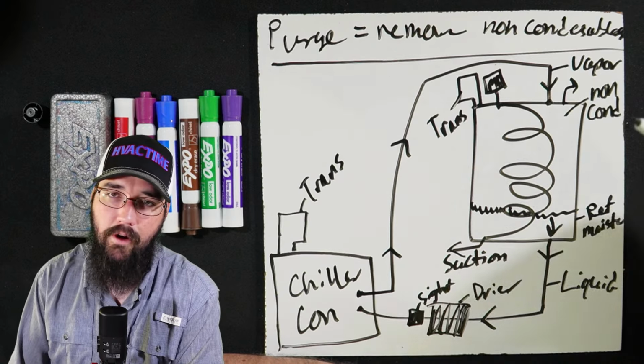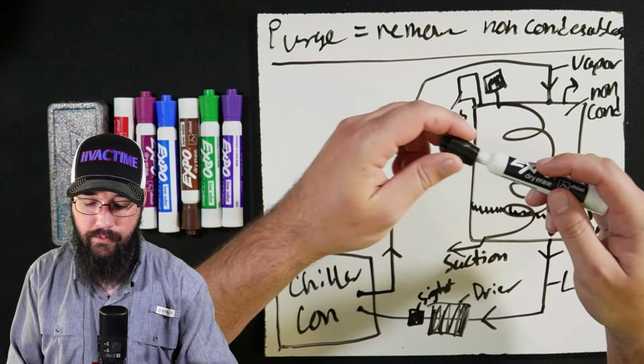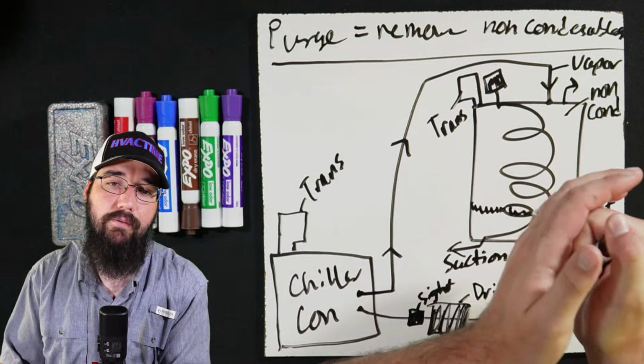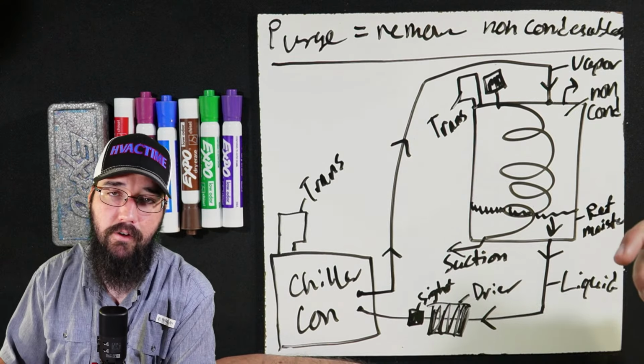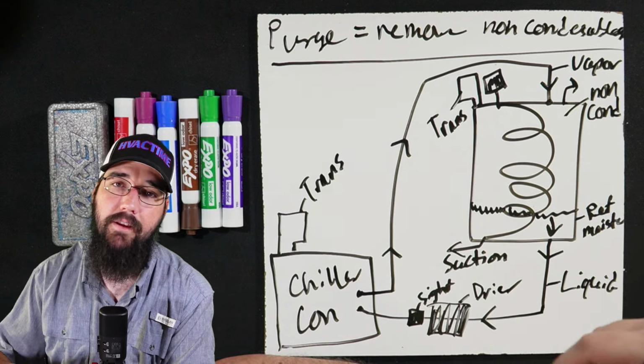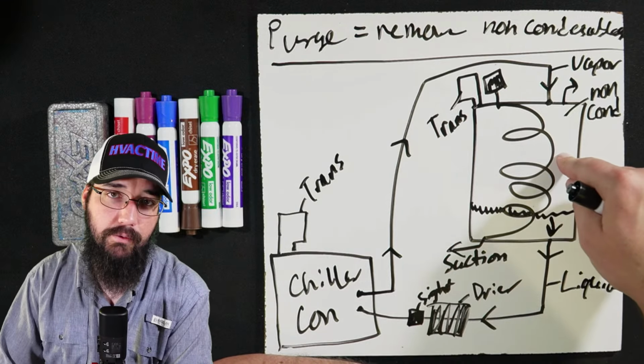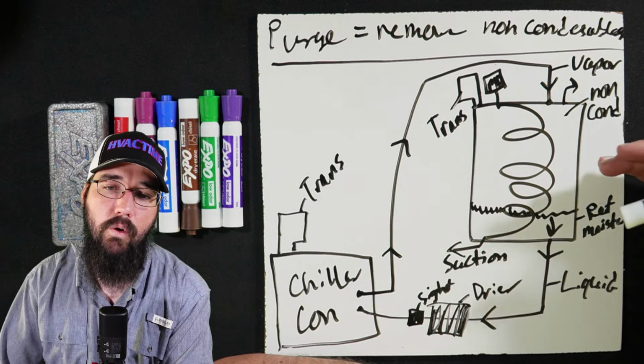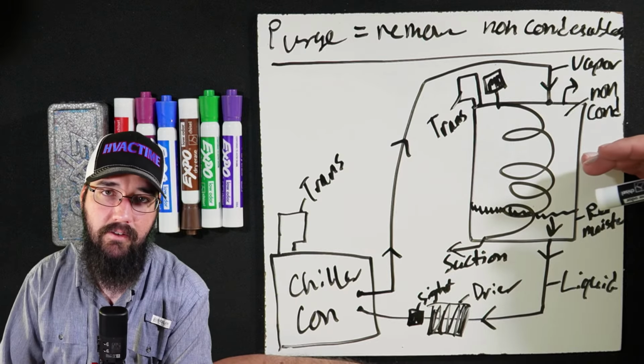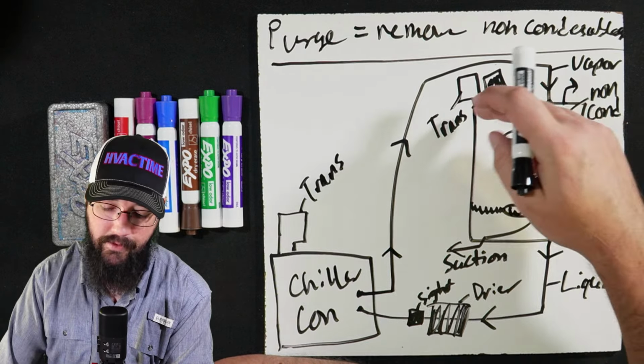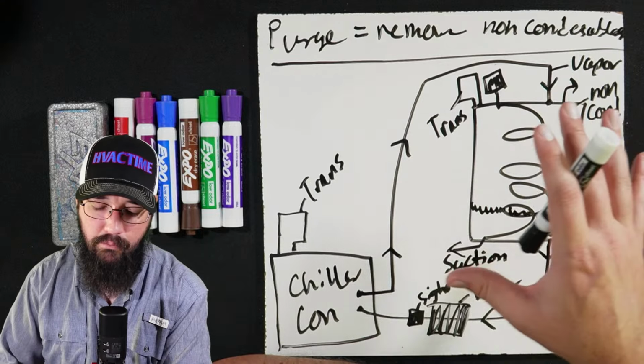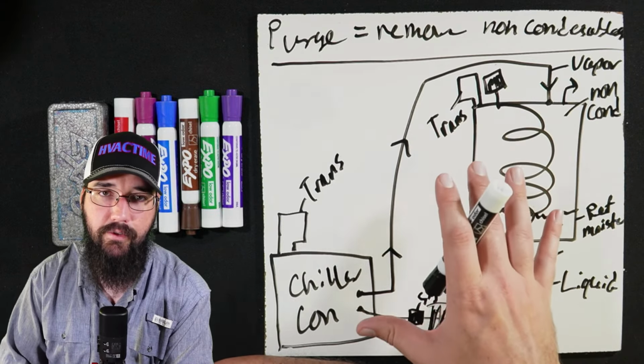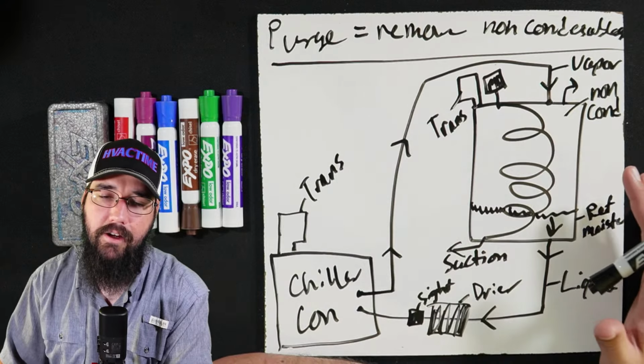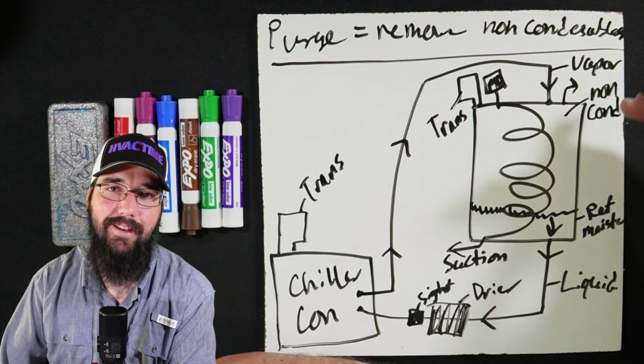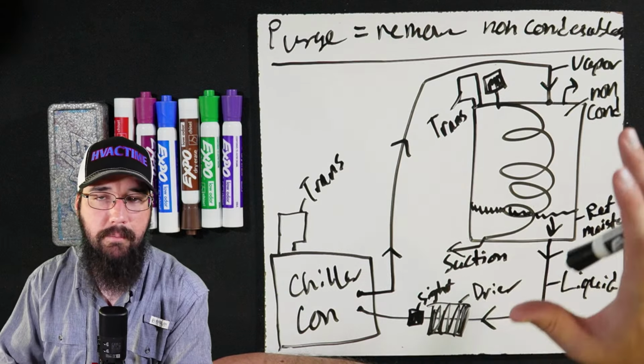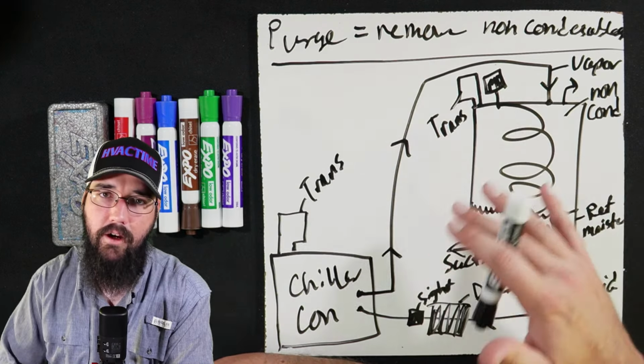Now, we are monitoring for that pump out time, so if we do have too much pump out time, that will start to trigger alarms for excessive pump out. That means that we have major leak issues, or there's an issue with the purge unit. Something is going wrong with the system that we're having to have excessive pump out. Maybe we've got a transducer or sensor issue somewhere. Something like that could happen, causing an excessively high pump out state, more than just a leak. It may not actually be a leak issue. Could be other conditions.